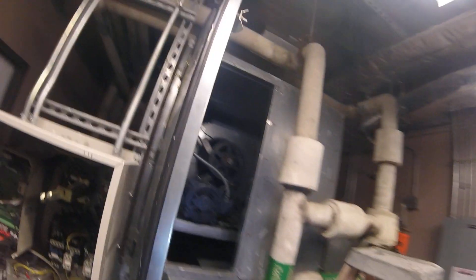This motor's been replaced about a year ago, 8-2-16. And like I say, I did an insulation test on it and I don't think the motor is bad. The insulation is good, it's not grounded, and like I say, it'll run in drive.